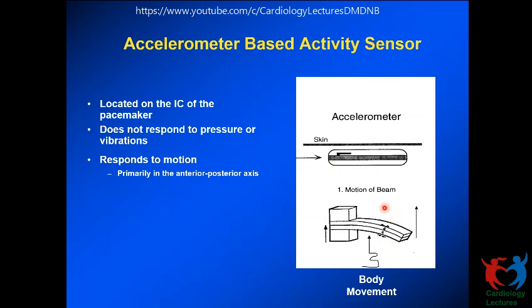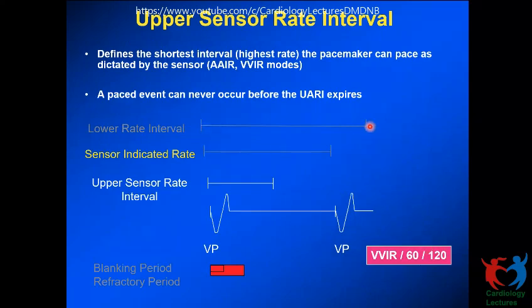Don't confuse this with the sensitivity or the pacing potential. This is a small potential that comes from the piezoelectric crystal that is proportional to the activity the patient is doing, which by means of an algorithm is converted into the level of activity and the corresponding rate at which we want to pace. So we program a lower rate, in this case 60 beats per minute, and an upper sensor rate of 120 beats per minute. The pacing rate would be anything between that, determined by the sensor, anywhere between the lower rate and the upper sensor rate.